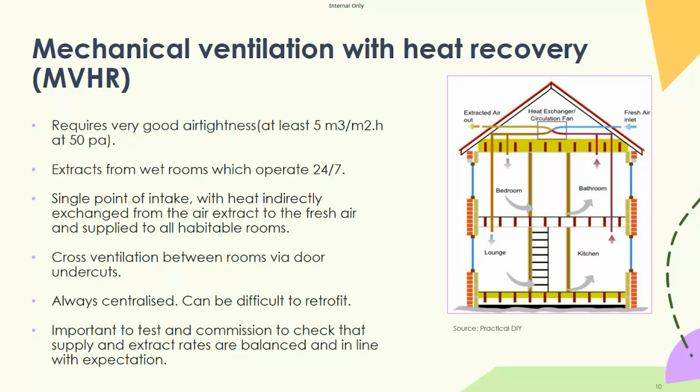And that just adds a degree of efficiency, so you're no longer dumping heated conditioned air straight to outside. You're preconditioning it and offering this supply air to other spaces in the home. But frankly, as great a system as it is, it's very difficult to retrofit, as many will appreciate. Running supply and extract ducts to upstairs and downstairs isn't always very practical.